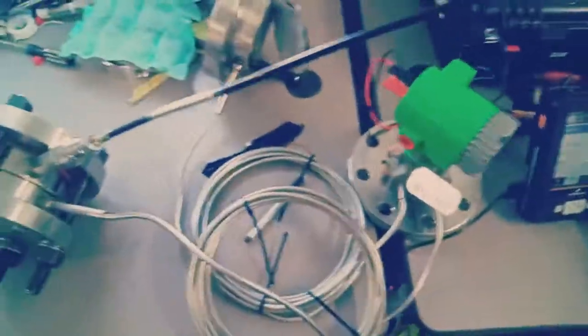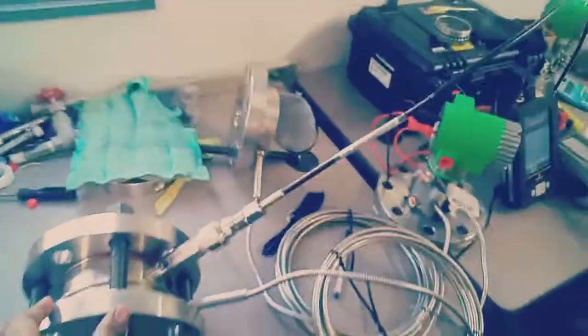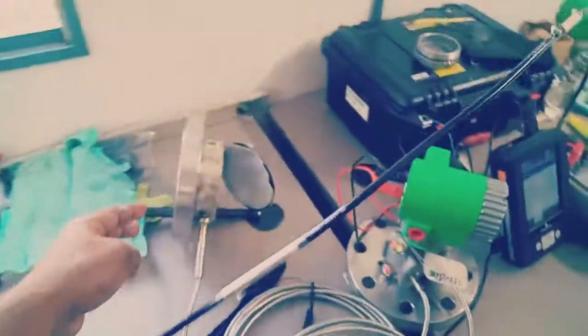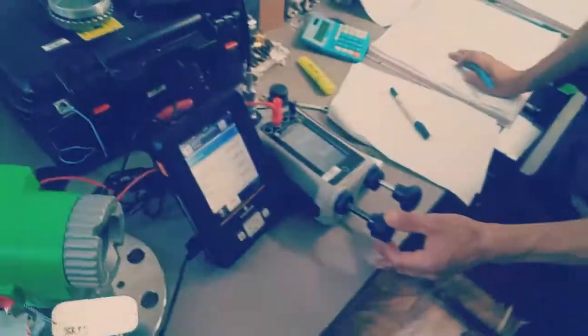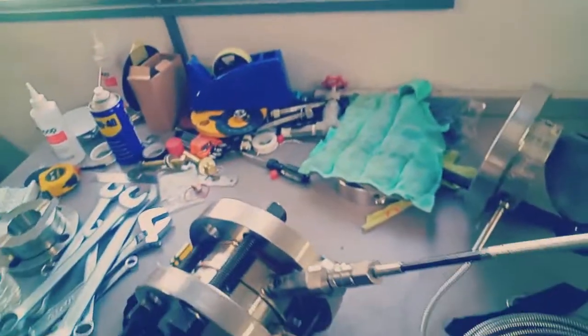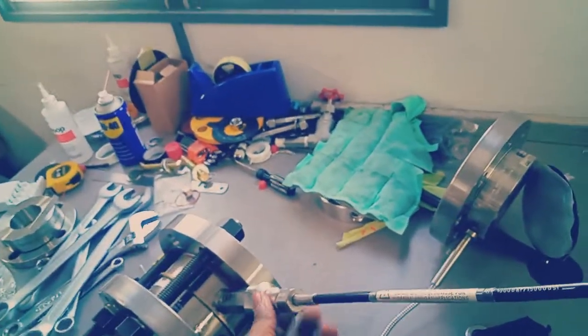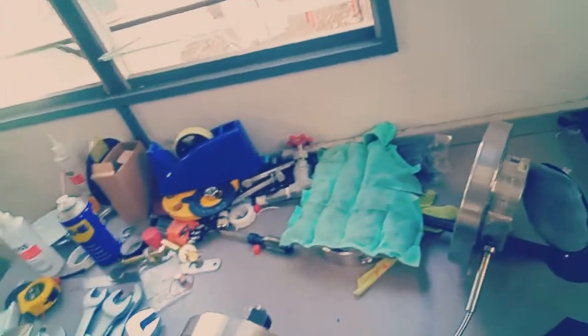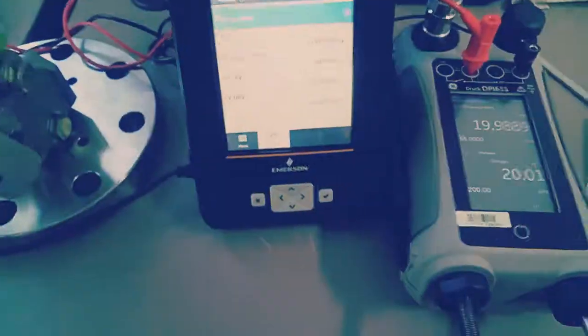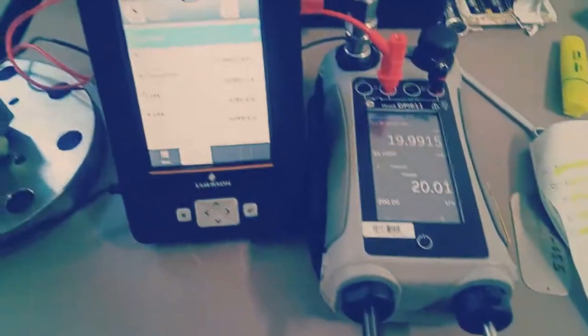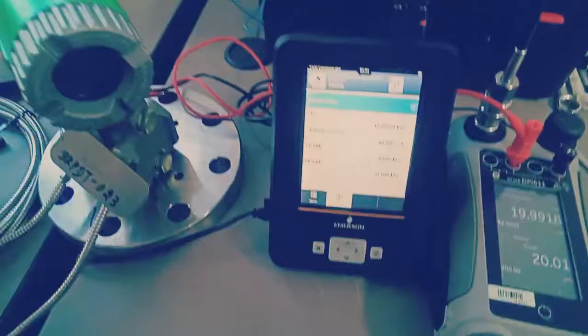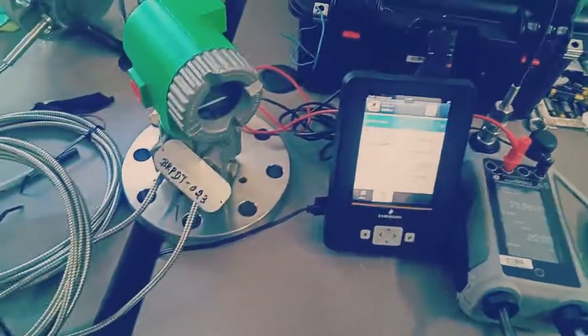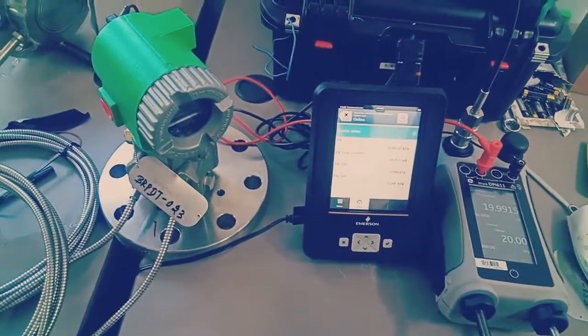You can see the transmitter mounting here, how we connect it. This is the HP and this is the LP, and the capillary is connected to the transmitter. The pressure hose is directly mounted through the flush ring, so the pressure is injected through this way. This is how we do calibration, and this transmitter has passed all the values, all five values. Thank you.